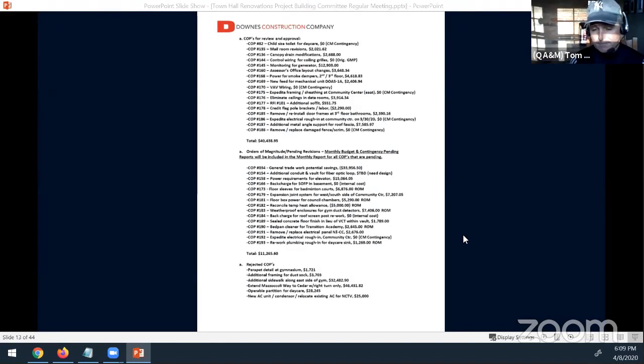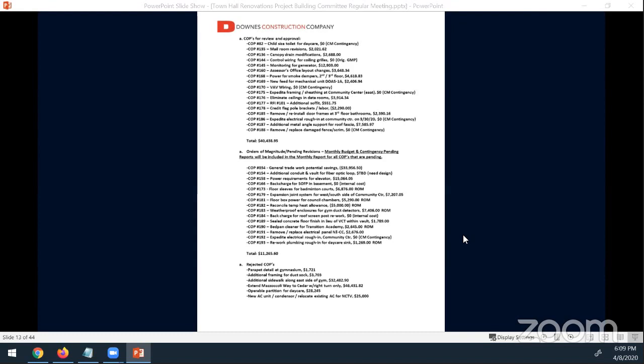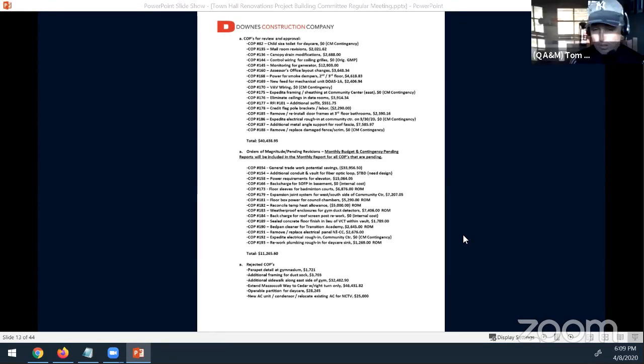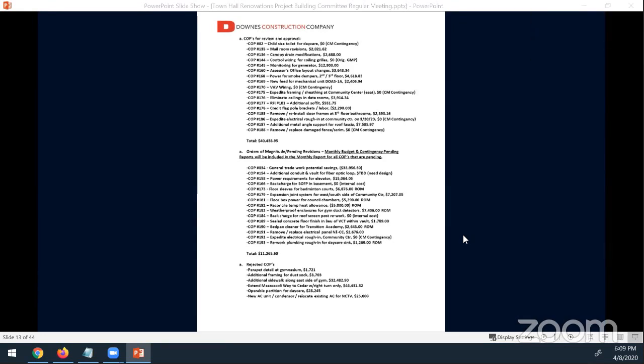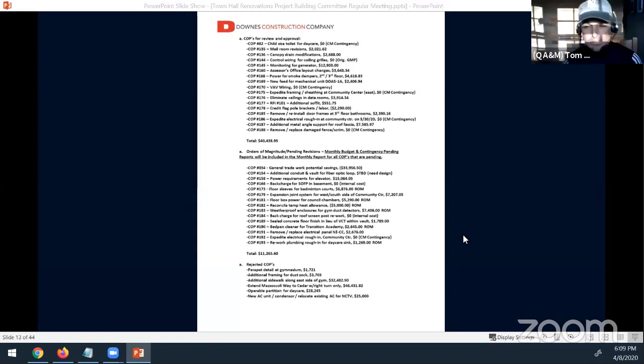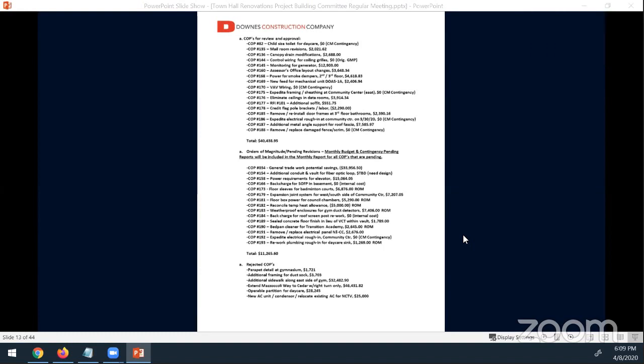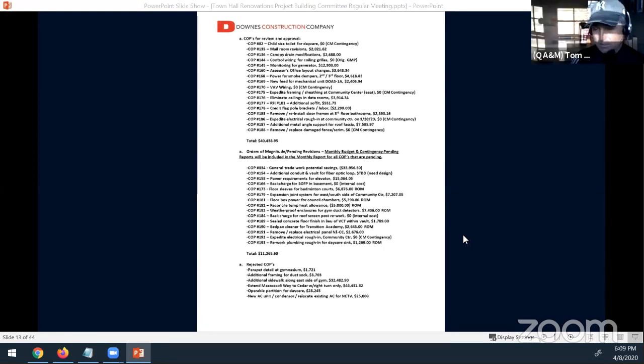So the two items that are left to essentially add to the generator would be the remainder of the lighting, or some of the lighting, as well as all of the cooling. Oh, and then there was one other thing: currently, the building on the generator has about approximately 200 power outlets, electrical outlets on the generator. So you could potentially add some more power circuits if you create more space.